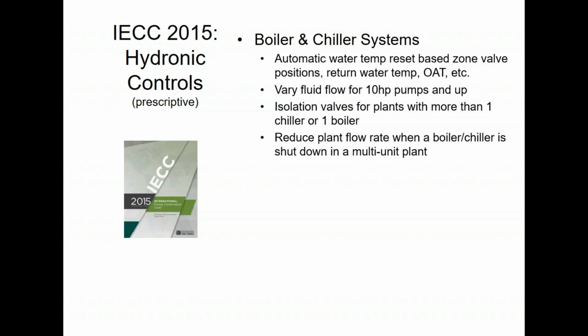If you have hydronic systems that have 10 horsepower pumps or larger, they have to have variable flow. They got to have a VFD on them, essentially. Or if they're small enough that you can get one, you can get an ECM motor on there that's variable speed. Either way, but they have to have variable flow if they're 10 horsepower and greater. You have to have isolation valves if you have more than one chiller or more than one boiler. That means if you're only running one of your chillers, you can only flow water through one of the chillers. The other chiller in parallel has to have valves that shut off to prevent flow from going through them and paying that extra pressure drop and that extra mixing.